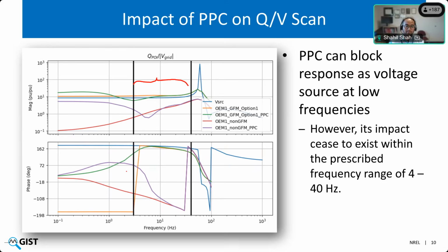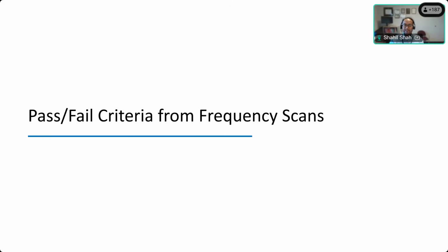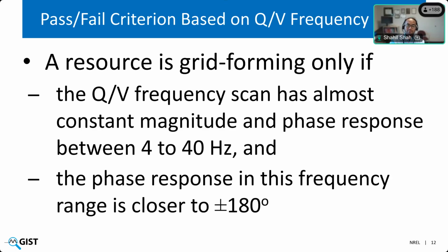Yeah, thanks, Deepak. So that was about the rationale behind selecting voltage source behind reactor as our benchmark, and the selection of the frequency range, frequency scan, and time domain testing. Now we will get into the different test methods we have included in the report, along with performance metrics. The first set of tests are pass-fail criteria based on frequency scan. We talked more about Q by V scans initially, and there are two other scans, P by theta and V by I. Similar rationale applies to those tests as well.